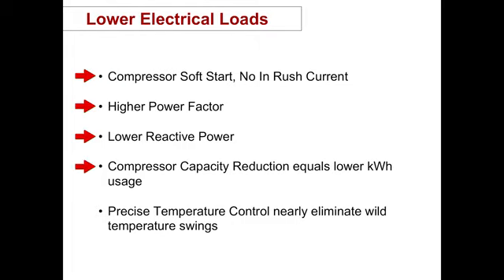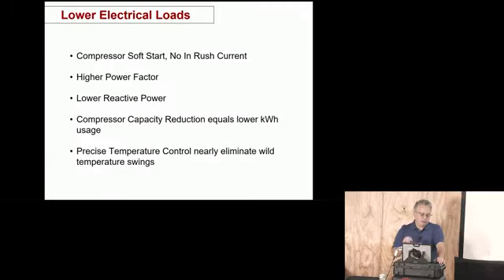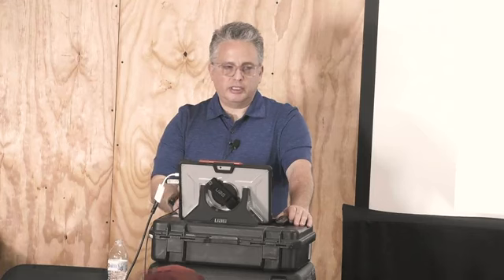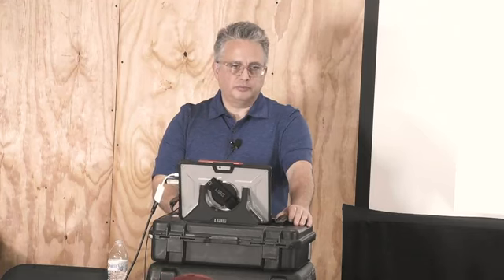Compressor capacity reduction equals lower kilowatt usage. Precise temperature control nearly eliminates wild temperature swings. So the only precise part of it is that the thermistors are fast reacting. It will sense a load change very quickly. And that could work to your disadvantage if it's installed incorrectly.